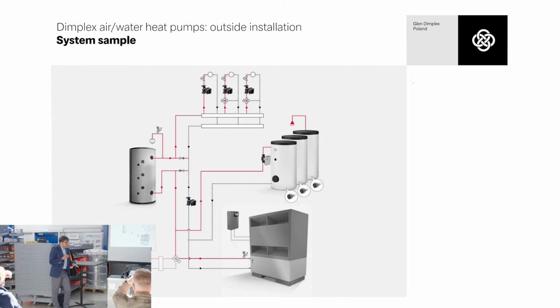The specific way we are using the buffers is that we are not connecting buffers in parallel between the heat pump and the rest of the installation, the outlet to the building, but we built this buffer tank in one row. The flow is directly to the buffer from the bottom to the top, and then to the manifolds, to the circulation pumps. But there is some tricky stuff in this diagram. We use a special manifold, 2 bypasses with non-return valves, for separating the hydronic from the primary circuit with this circulation pump to the secondary circuits with, in that case, three circulation pumps dedicated for the internal installation. So if there are some overpressures, these 2 bypasses can spread it and fix the overpressure.